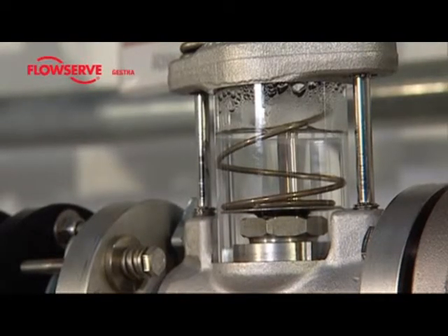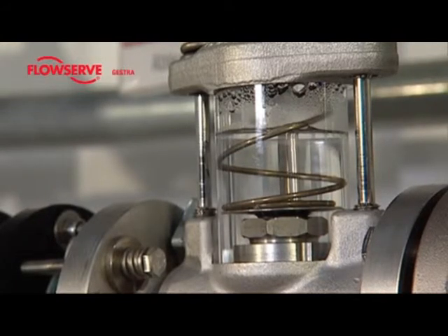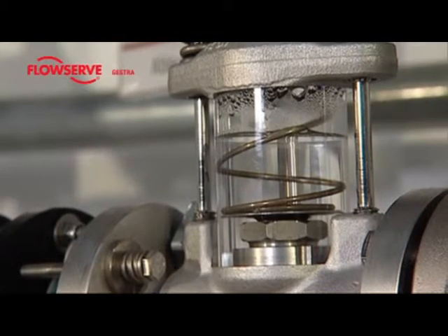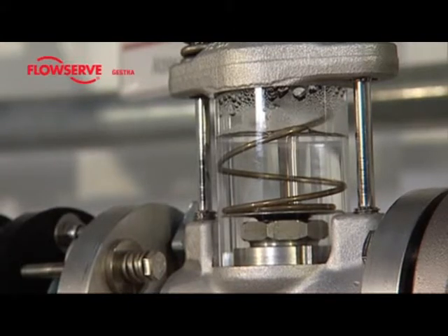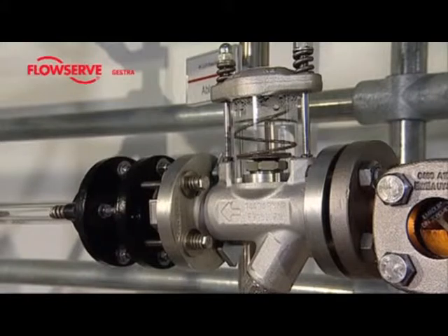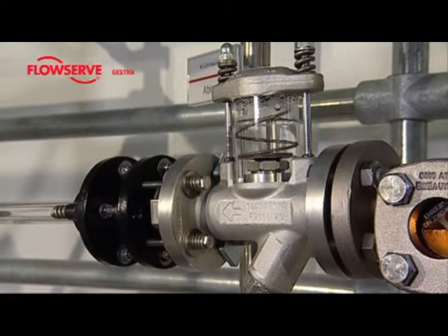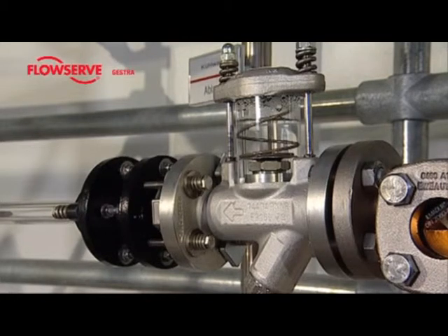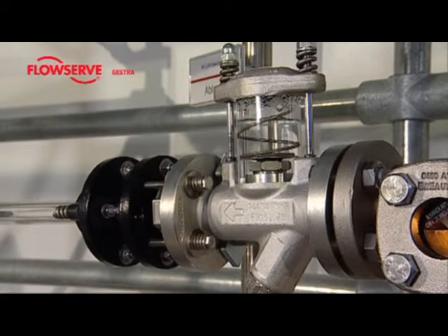With the model shown here, a capsule with a flat seat is installed as the regulator. A glass cylinder lets us look inside the membrane steam trap and observe the flow conditions prevailing there. At the start of every heating process, there is still air in the heat exchanger. Air or other non-condensable gases must be vented from the heating process by the steam traps, since they will greatly impair the exchange of heat.